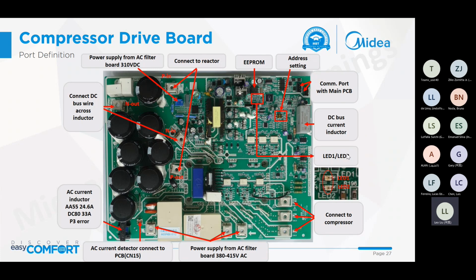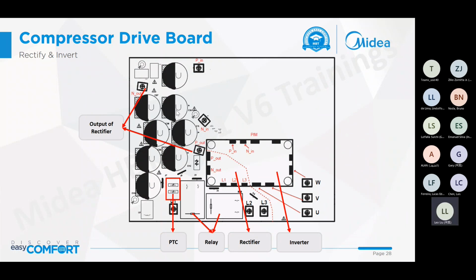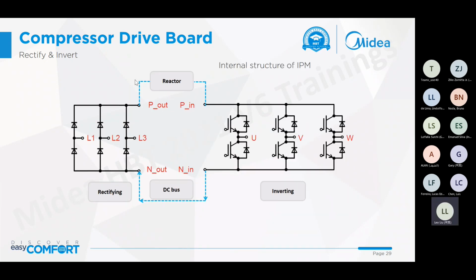It can detect the current value. If the current value is more than the limit, there will be an error code here. The rectifier and inverter are the main functions of the compressor drive board. So this is the diagram. The power supply is rectified to the DC bus reactor. Then from the output you get the power supply for the compressor's 3 terminals, and the inverter gives adjustable voltage for the compressor, so with different capacity output.